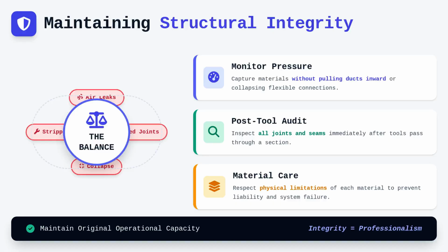Structural integrity is a constant variable you must monitor while performing cleaning operations on any air handling system. A poorly managed cleaning process that exerts too much pressure on duct joints or plenum seams can lead to air leaks that were not present before your arrival.